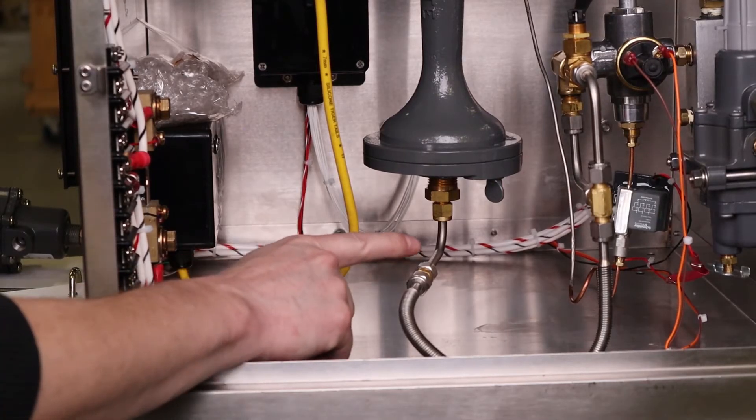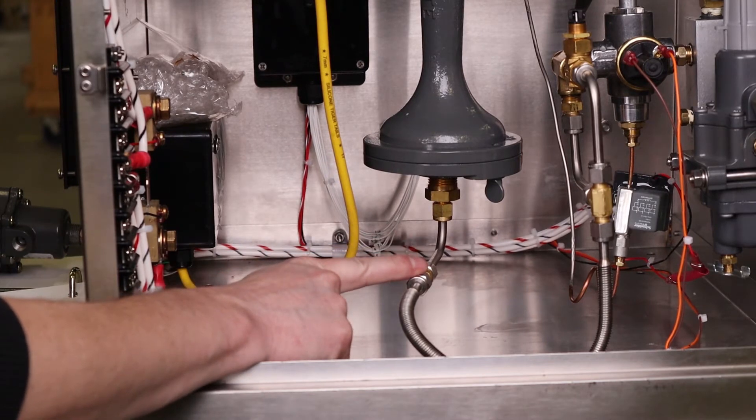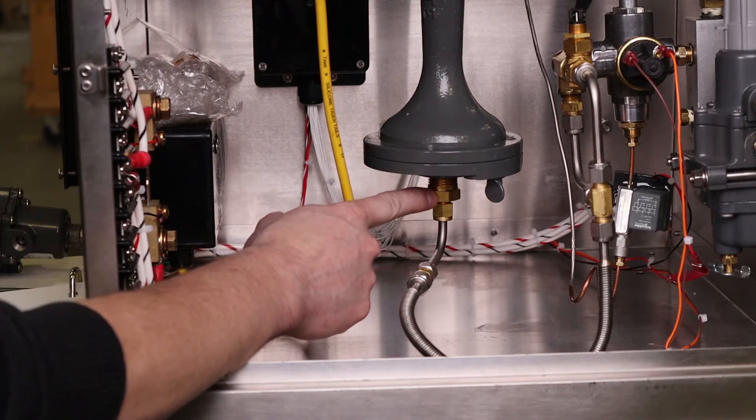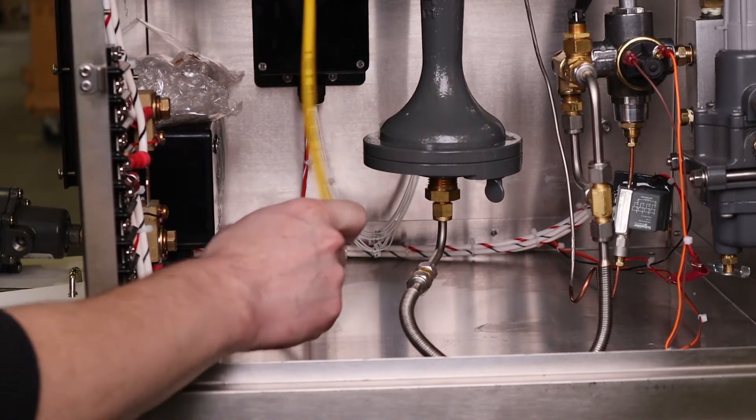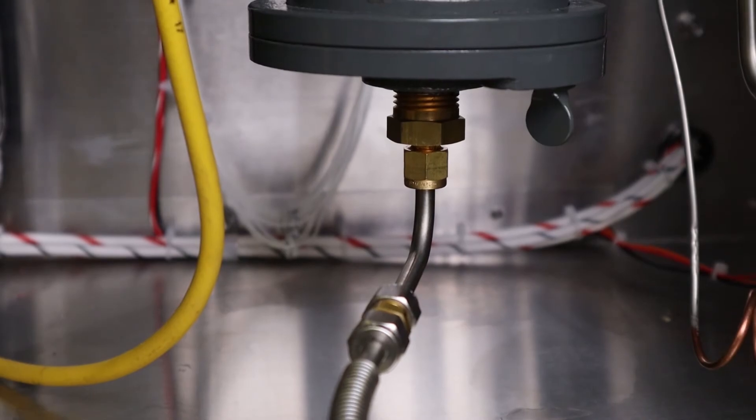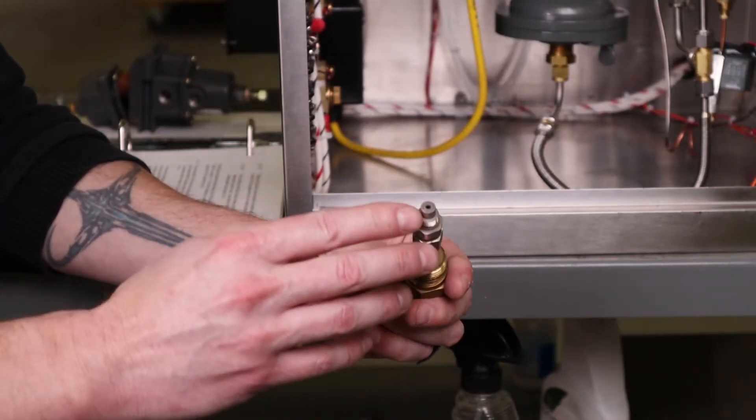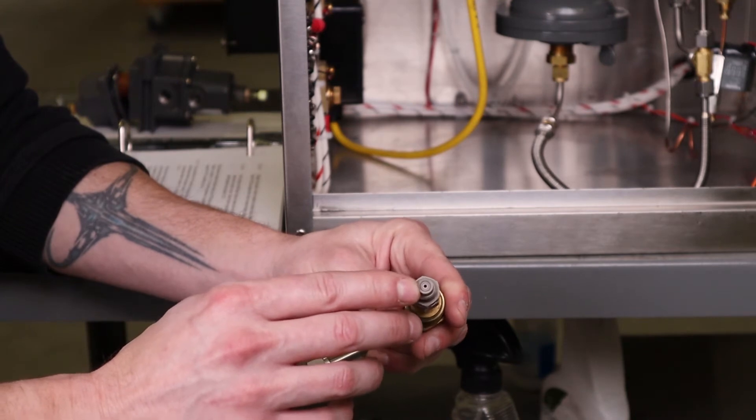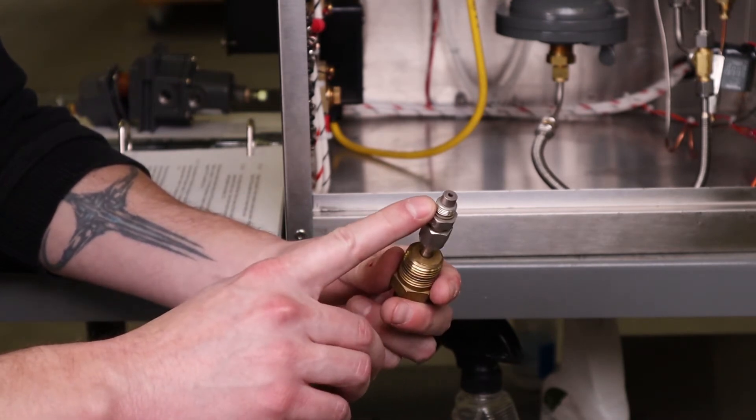Next you'll use a 9/16 wrench to loosen and remove the flexible fuel line and a 7/8 wrench to remove the fuel orifice. Inspect the tip of the orifice for any debris or clogging and if so, remove and replace it.